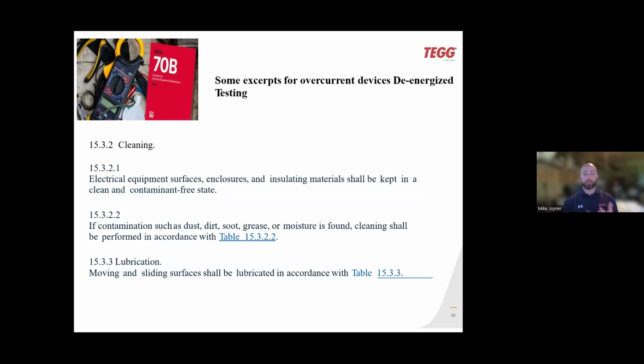And then this gets into the cleaning for the de-energized maintenance we were talking about. We go in there, we start from the outside in. We have shut down buildings. Like I said, there's a will, there's a way. We've shut down numerous different types of buildings and occupied buildings. We start from the outside in. We clean the outside. We make sure that it is actually bolted down to the ground. We check for any kind of violations once everything's opened that you normally can't typically do during the regular infrared scanning or maintenance site visit.